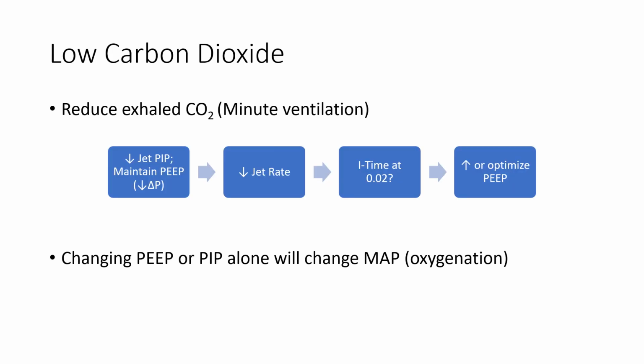If the carbon dioxide levels are low, the first step is to decrease the PIP. If unsuccessful, then the rate should be decreased. If these steps are unsuccessful, ensure that the inspiratory time is at 20 milliseconds if it was previously adjusted. If none of these are successful, the PEEP could be increased as the mean airway pressure may not be optimal. However, keep in mind that adjusting the PEEP will change the delta P and should also be adjusted accordingly.